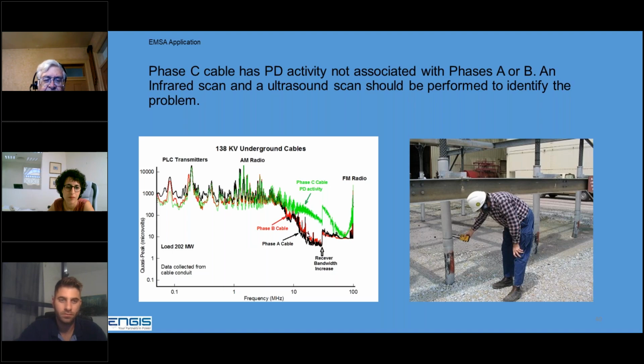Alpha and Bravo phases are basically the same. The Charlie phase is higher. And using the sniffer, we also verified that the Charlie phase was higher. So, okay, what do you do now? Well, you can do an infrared scan, or an ultrasonic scan, or maybe use a coronoscope to see what the problem is where those cables attach to the transmission system. There'll be a pothead up there. There may be a potential transformer, a surge arrestor, a disconnect switch. So there's a lot of connections where these cables go into the grid. So we've picked up a problem. Now you need to apply some other tests to verify what that problem is.